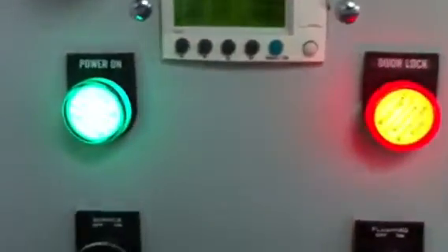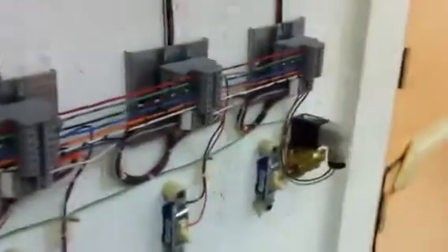The cleaning timer is when, with this other button over here, the flushing, we activate this, we're applying power to this solenoid valve, and therefore water coming in, water going out to the drain, start flushing the chute. And once again, this has a timer, so it's going to be flushing for 600 seconds over here until we turn this back off. You heard the pop now.